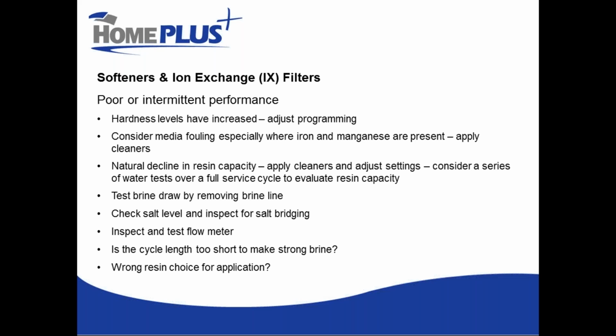So it's really important that we be on the lookout for problems related to the performance of our ion exchange and softeners. So one of our first considerations is, have our feed water conditions changed? Ideally, if you have test equipment on hand, you can do a quick test, compare that to your background levels, and see if any adjustments are needed. One of the most important programming parameters on a water softener is, what is my hardness level, or what is my organics level? And if your hardness levels are fluctuating and you're not making programming adjustments, you're going to have intermittent performance issues.